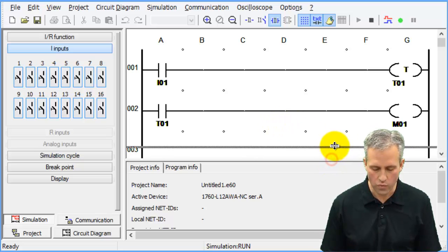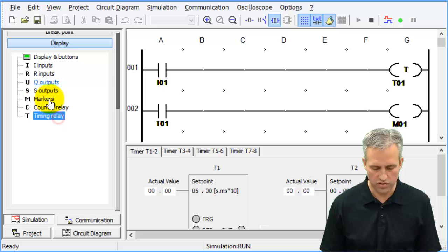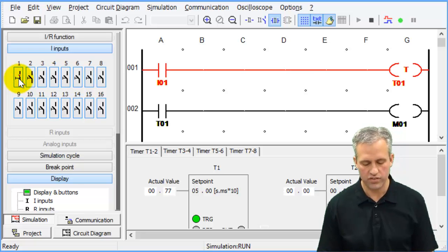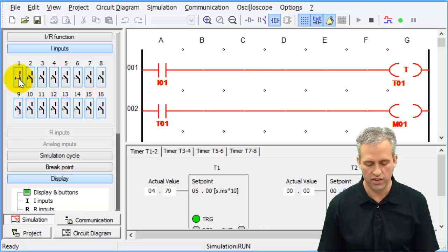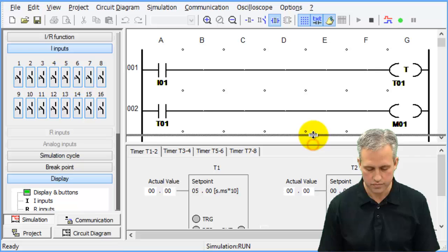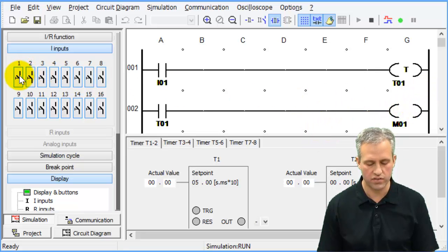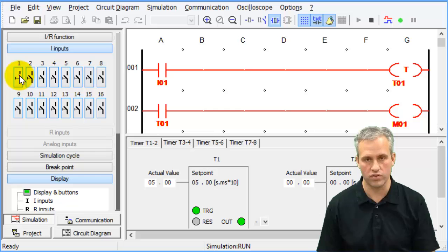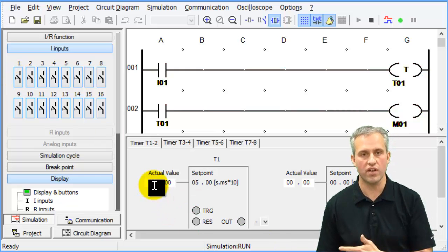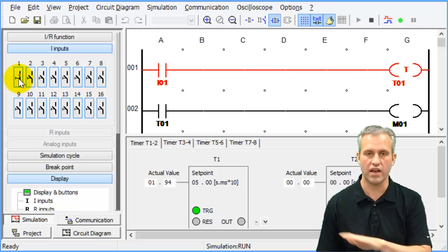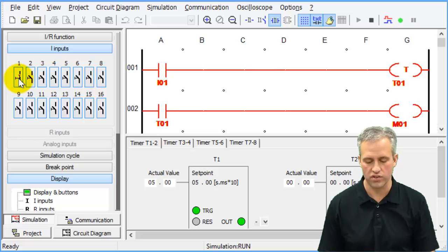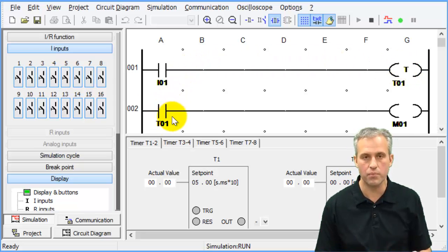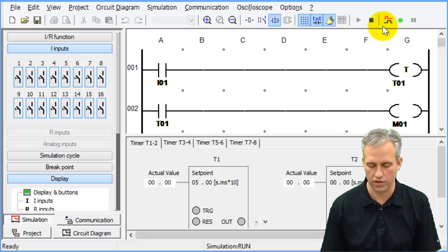Let's watch the timing displays. Hold down the input and you can see the value is actually counting. As soon as it gets to five, the next line comes on. The idea is you're trying to turn it on, but it has a delay before it comes on — an on delay of five seconds. As soon as you let go, it goes off instantly. No delay in turning off, just a delay before turning on.